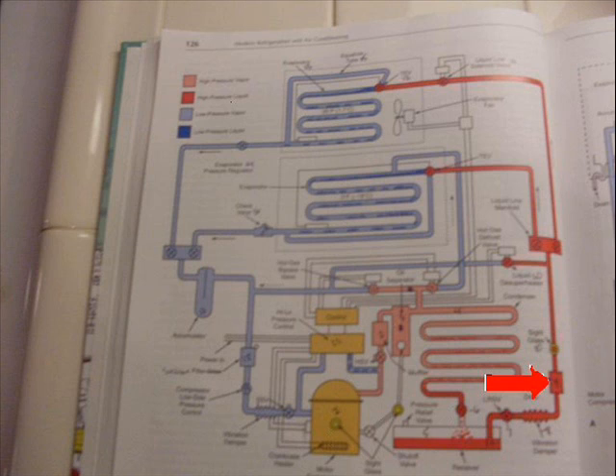Leaving the filter dryer, we go... Oh, last thing I should say. The filter dryer is to be replaced whenever the system is open for repairs. If the system had been open for repairs or the system had a leak, the filter dryer must be replaced. The filter dryer's job is to clean the new refrigerant, not your screw-ups. You don't put it in as an insurance policy. You install a filter dryer on every repair to clean the new refrigerant and make sure you don't have any moisture in the system at all.